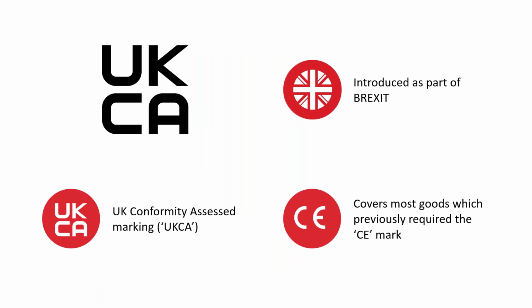Again, not just lighting. In the case of hazardous area equipment being installed in the UK, the ATEX directive was going to be replaced by UKCA, and the UK directive, SI 2016-1107, a UKCA EX scheme known as UKEX. And in addition to the notified body and QAN issued under the ATEX directive, a separate UK-based approved body and a UK QAN must be applied to products under the UKEX scheme.